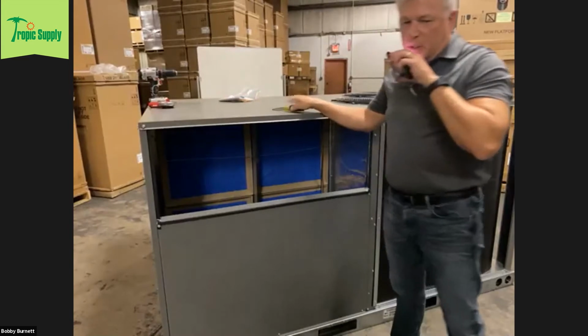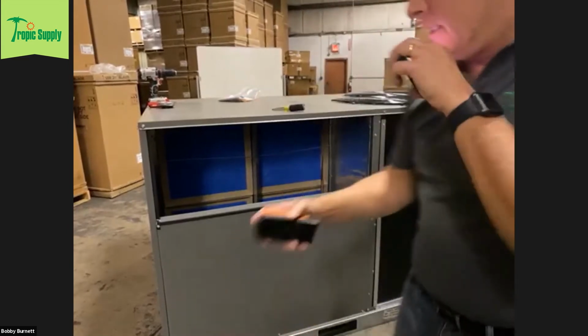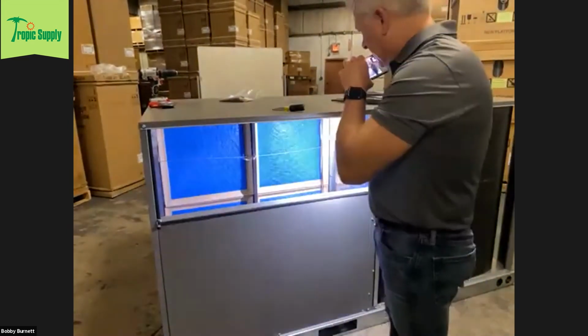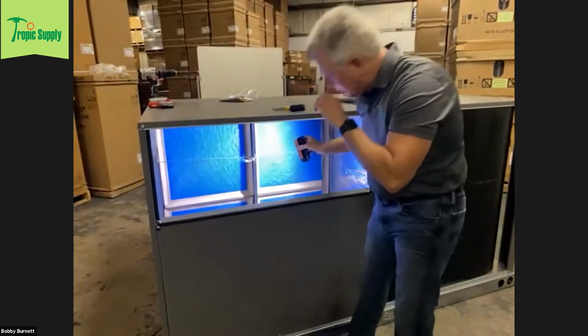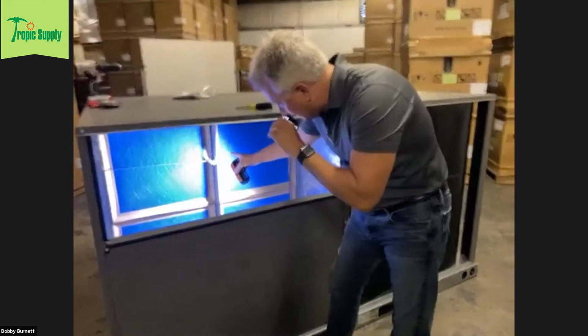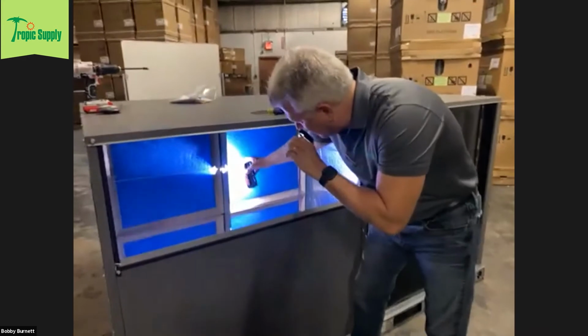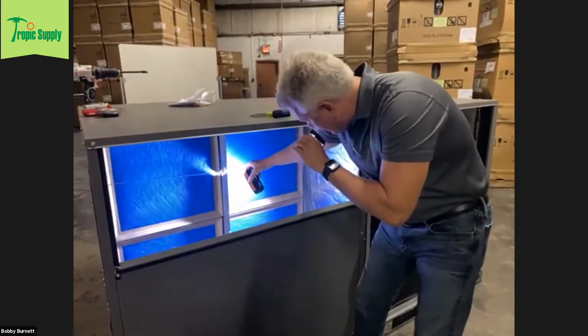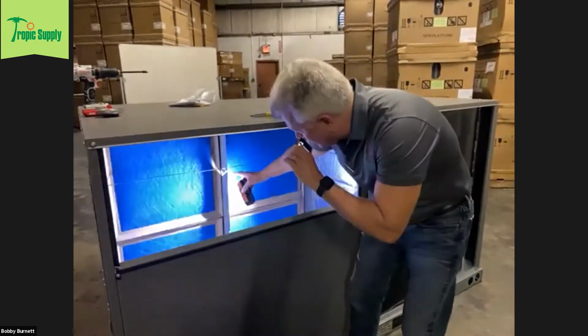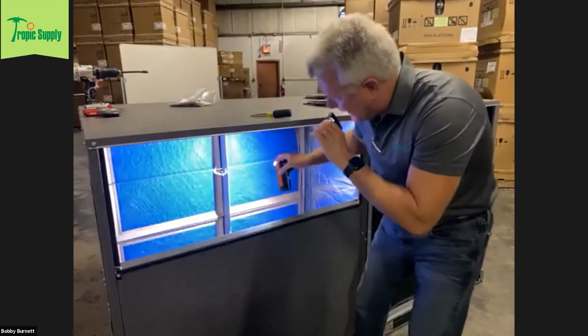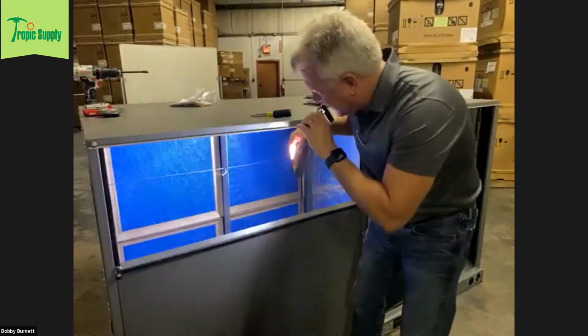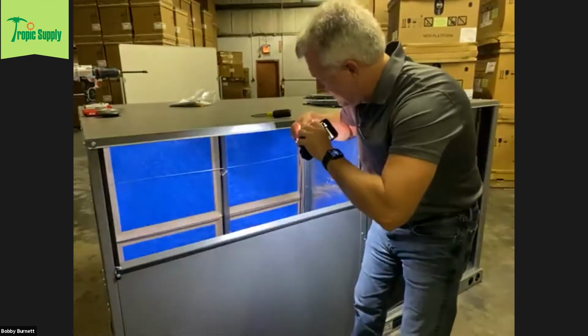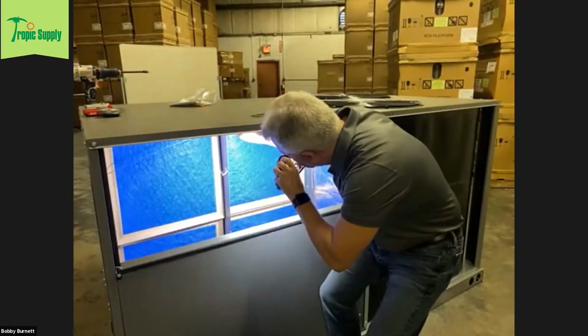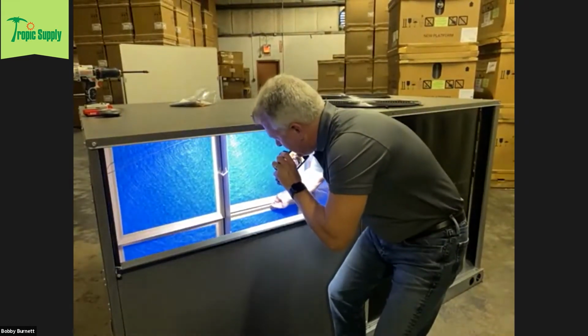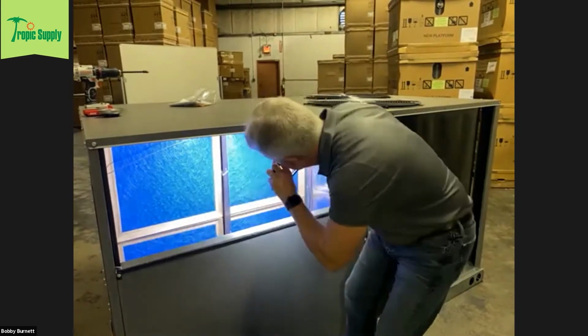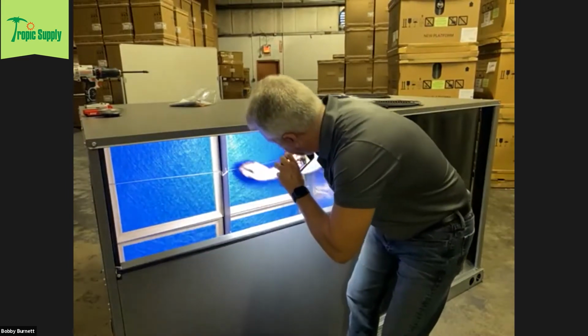All right, so when we remove this panel, what you're gonna see in here, okay, you've got 2-inch filters in here, and you have this rack available here, where with the 2-inch filters, you simply move this rack out to here, and now these will accommodate 4-inch filters. And to change those filters out is as simple as moving this up to here, and now you've got access to change these out, okay? Put that back down in here.